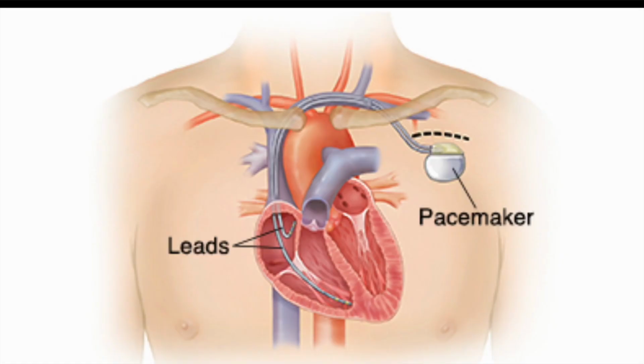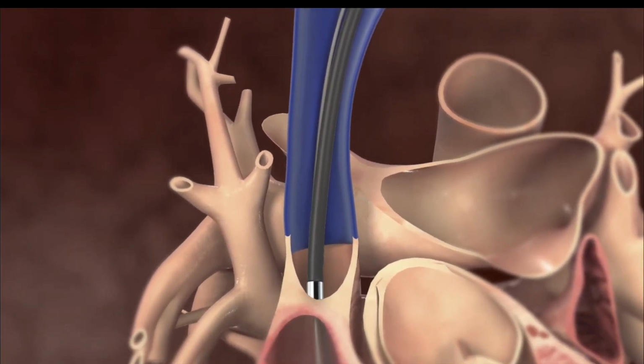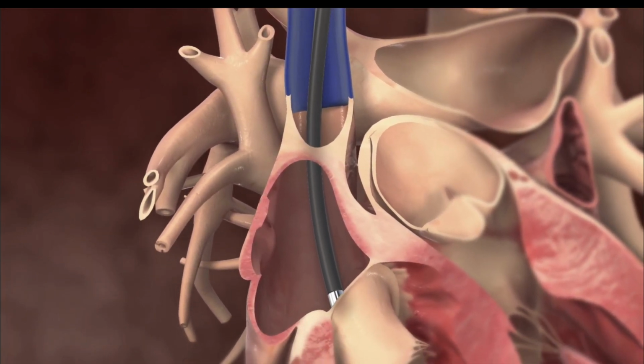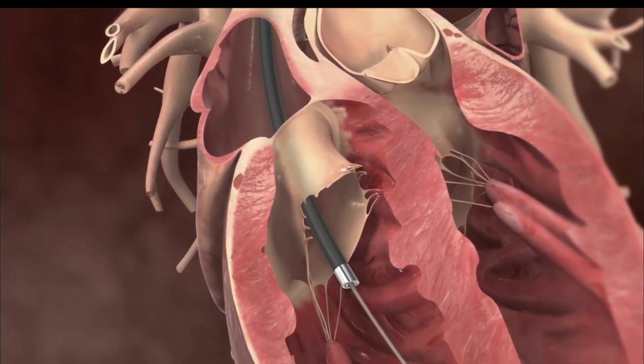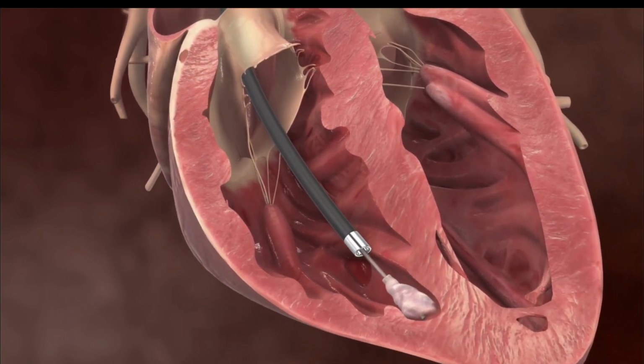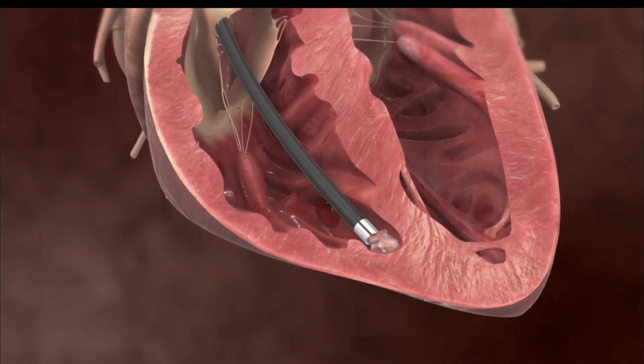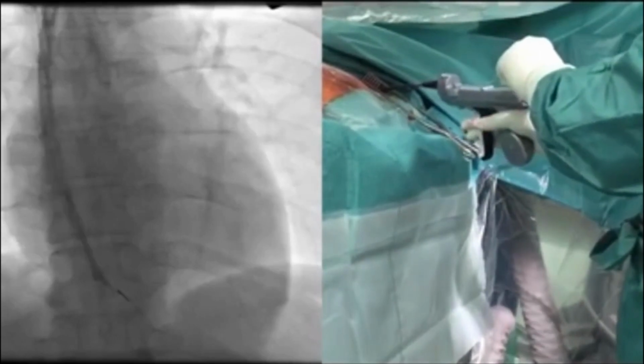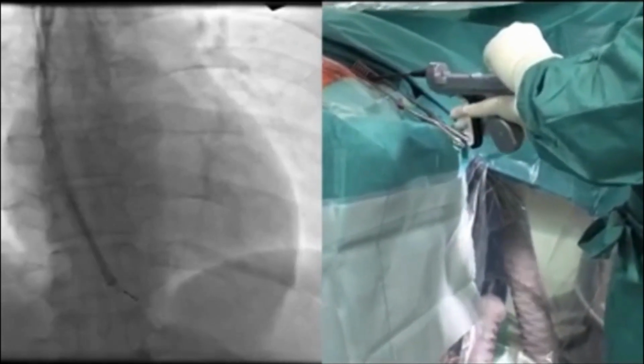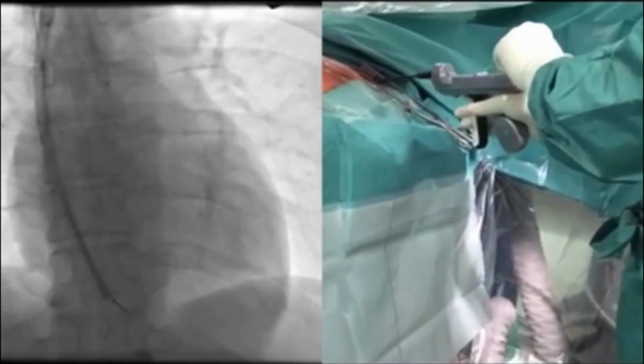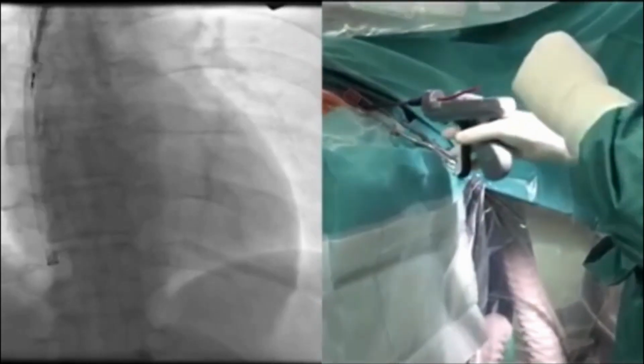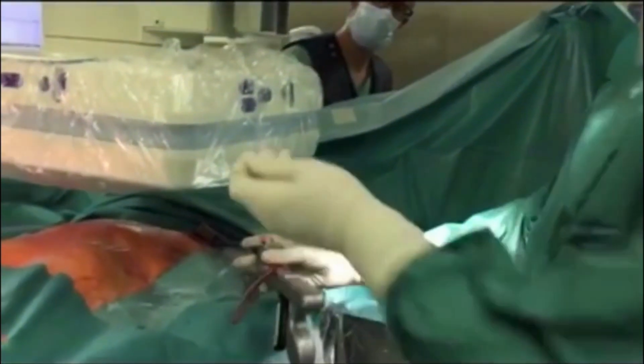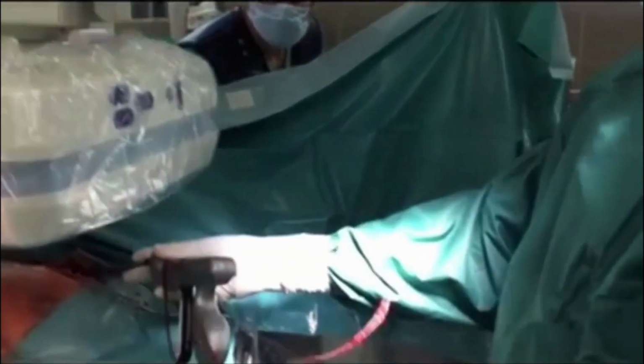Today, a typical extraction procedure begins with excising at the pocket where the generator sits under the skin and detaching the leads from the pulse generator. To help the physician pull the leads back out of the vessels, a sheath, which is a hollow tube, is typically slid over the lead until reaching the distal end, or where the lead is implanted at the heart tissue. The physician then engages in what's called traction and countertraction, or pulling on the lead while simultaneously pushing the sheath into the heart tissue to dislodge the lead tip. The leads are then pulled back through the subclavian vein and the procedure is complete.